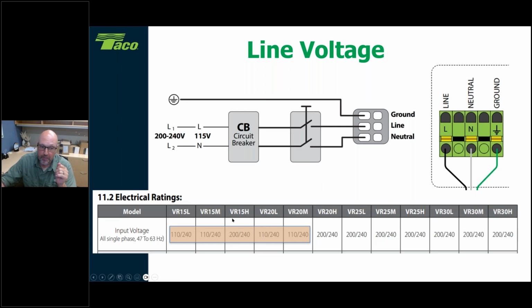So you put 110 to the 15H and it's not going to give you the full speed you're looking for. So these are not different models. The beauty of this circulator is, depending on what you've got there is how you can hook it up. So the VR15L, you can have 110 or you could have up to 240. You could have 200, 208. You can just drop it right into the terminals and rock and roll and you're ready to go. All right, but just make sure you pay attention to which model here and what power you can run to those circulators. So that's been, and remember again, these are all single phase. It is not a three-phase pump. These are all single phase ECM wet rotor circulators.